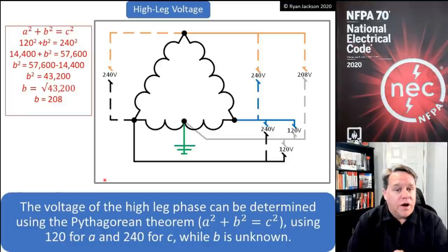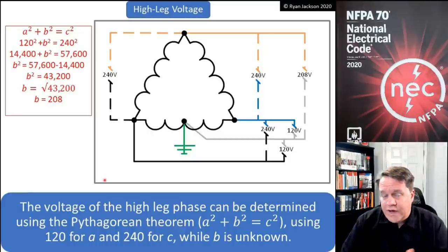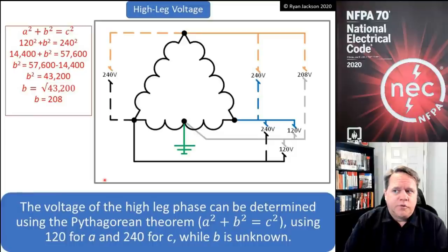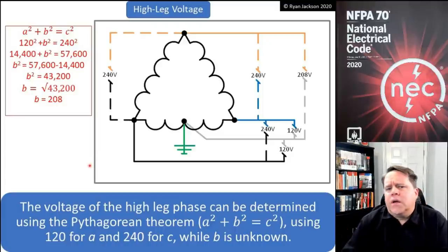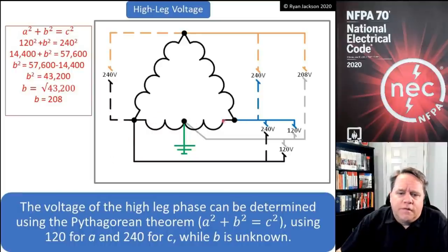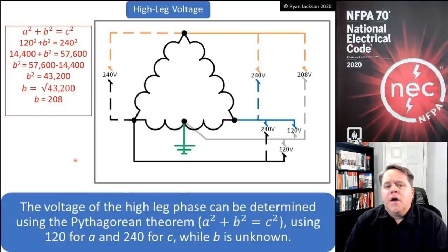If we have a Delta connected transformer we can connect it in three different ways. We can have an ungrounded system, where the transformer windings are not connected to earth at all — those are pretty rare. We could also have a corner grounded system, where we take a corner, pick a phase, and connect it to earth and the metal parts. Or we can have a high leg system, which is where we take the middle of one of the phases and connect it to earth and also to the metal parts, and that creates a neutral point.